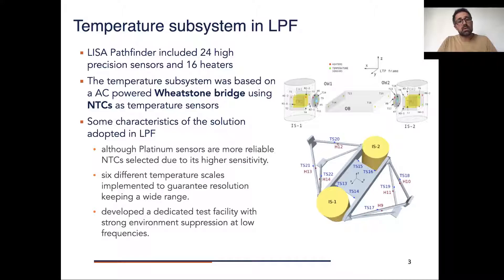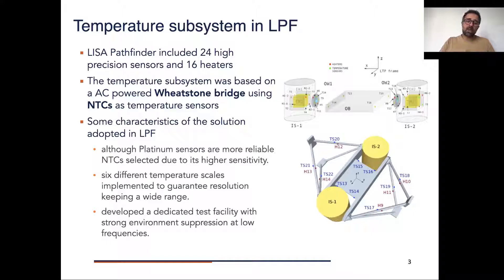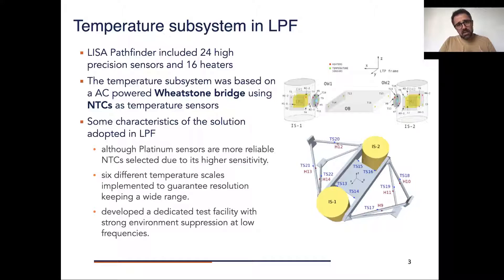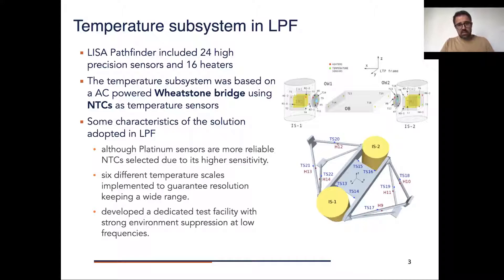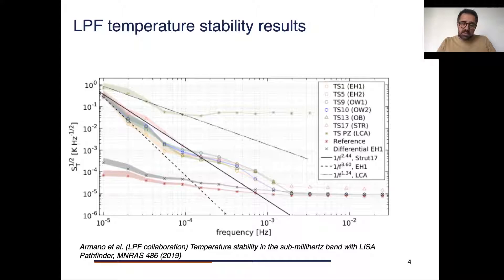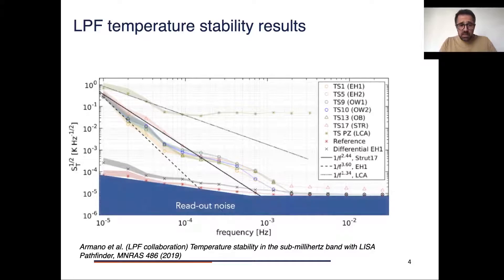The basic idea behind this temperature measurement system was to use an AC-powered Wheatstone bridge using NTC sensors. The basic characteristics are: we were using NTC sensors instead of platinum sensors because, although platinum sensors are more reliable, the NTCs are much more sensitive. We were using six different scales to have a wide range of temperatures, but with high resolution on each scale. An important part of the development was also building a test facility where we could suppress environmental temperature fluctuations to validate the electronics and subsystem.